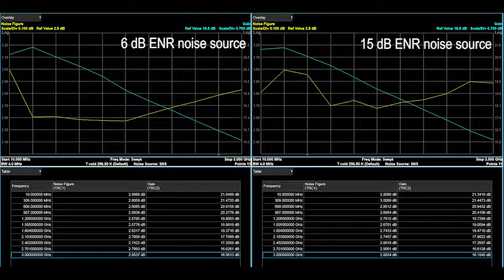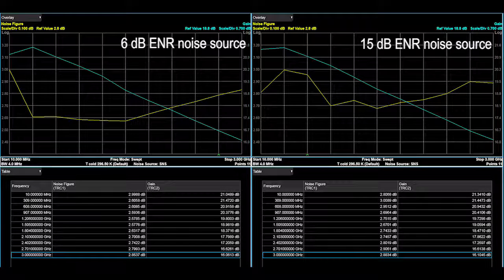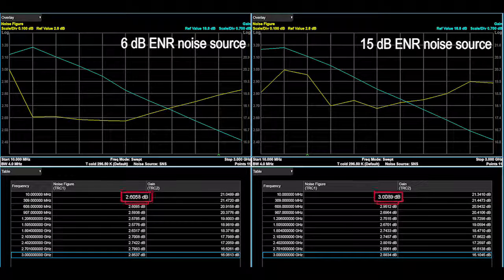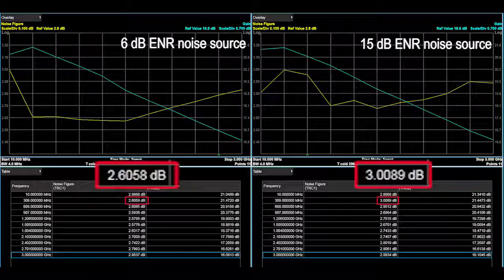Here is a comparison between a 6 dB and 15 dB ENR noise source. Notice how the 6 dB ENR noise source results in lower noise figure, which we can also verify by looking at the table readout. In this situation, choosing the correct noise source meant a difference as large as 0.4 dB.